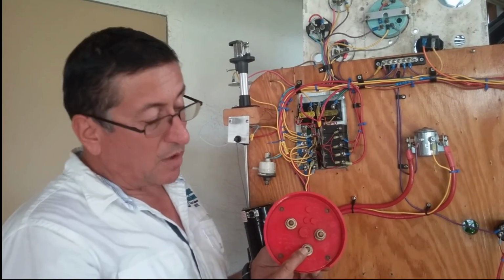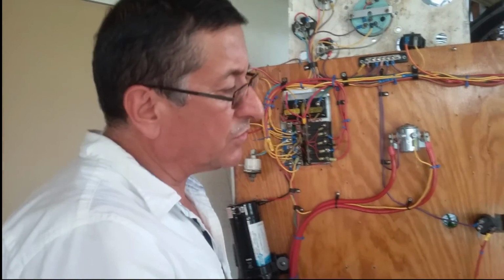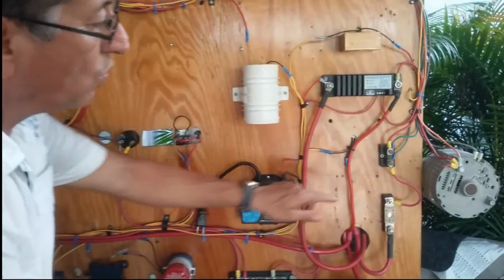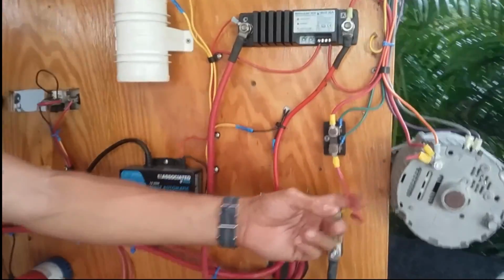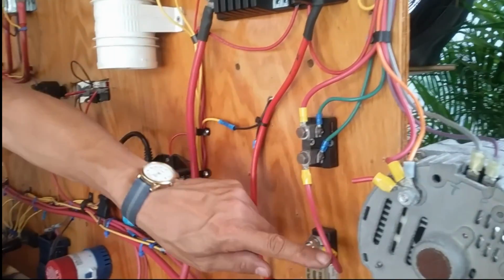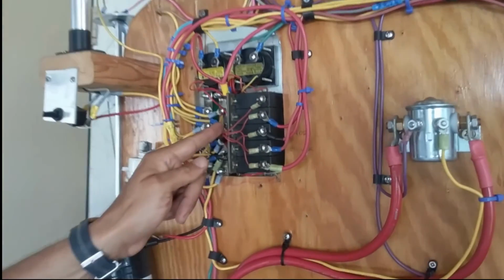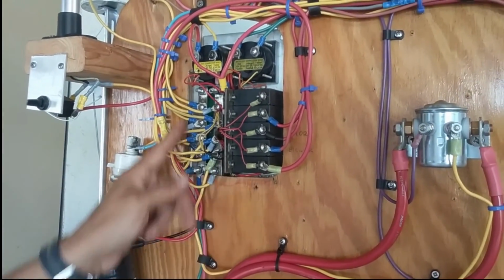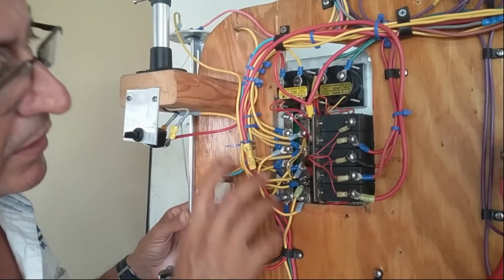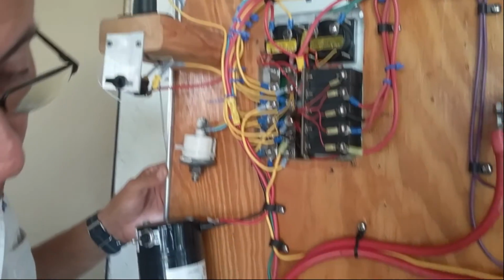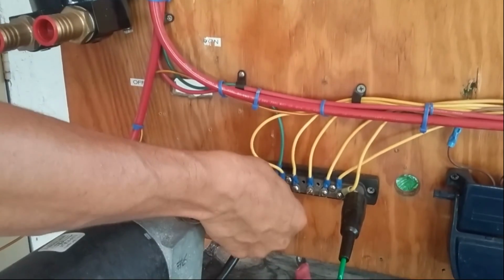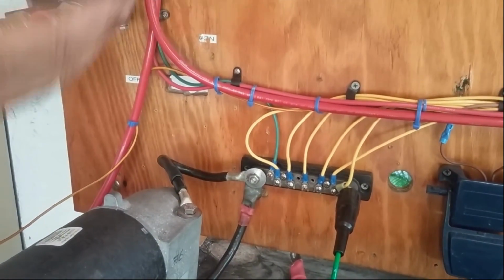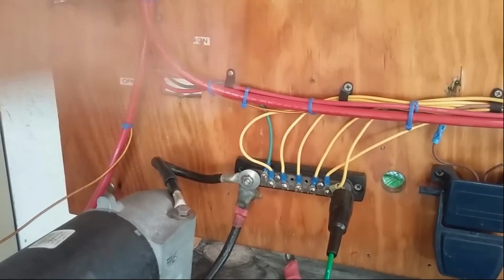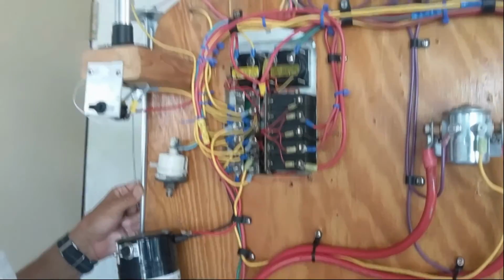And from the common, we have two cables. One small wire for the panel, and this is the wire going out to the panel and entering here into the positive bus bar on the panel. The negative bus bar of the panel is connected with the main negative bus bar, located normally in the engine room or pretty close to the DC panel.